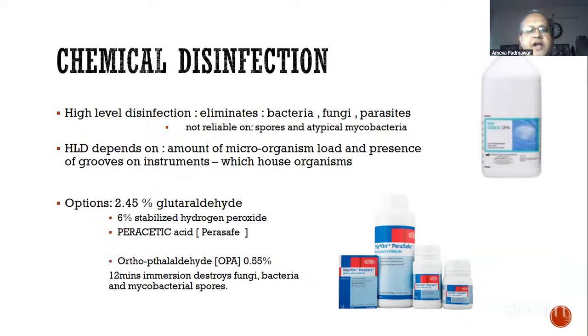Okay. And there are certain strips which are given by the supplier, which have to be dipped in the solution in the beginning of the day to know whether you can use it through the day. So it is a good practice to use these indicator strips, and do not, I'm telling you, do not reuse this solution if it has become hazy or cloudy. Okay. So you have the options in the form of 2.45% glutaraldehyde, or aldehyde free, something known as orthophthalaldehyde, that is 0.55%. This requires lesser time for disinfection and is a little bit expensive, but for fast disinfection, it's a good modality.